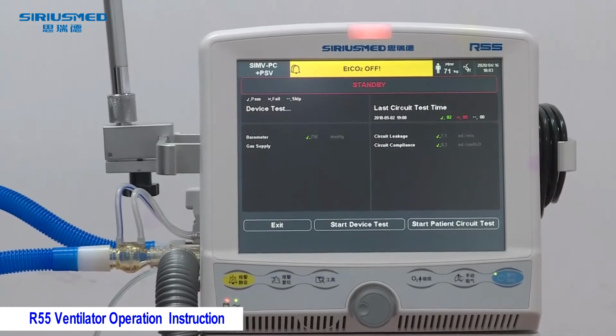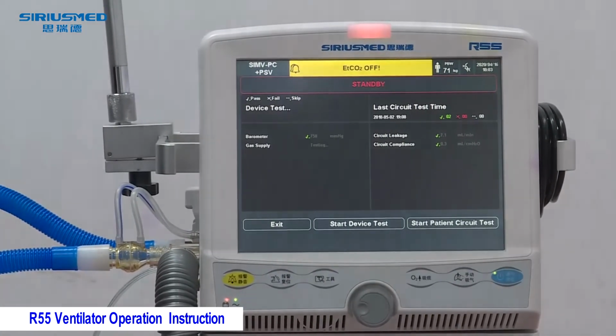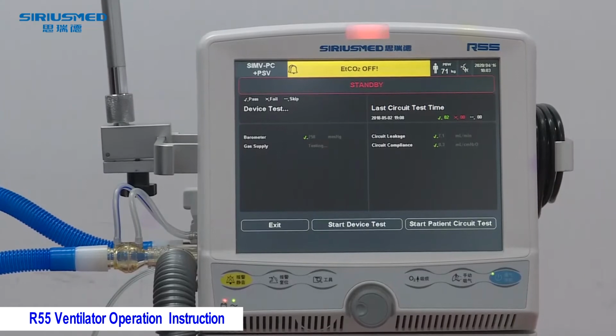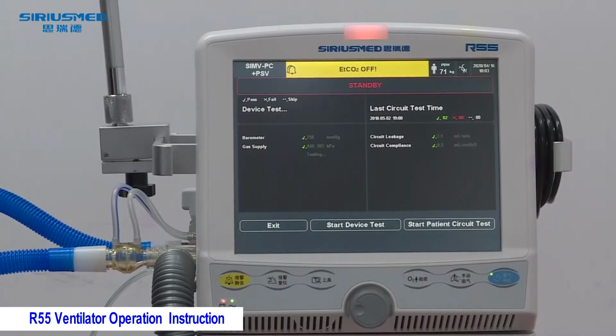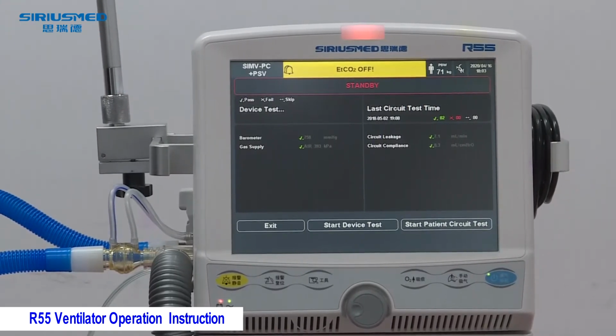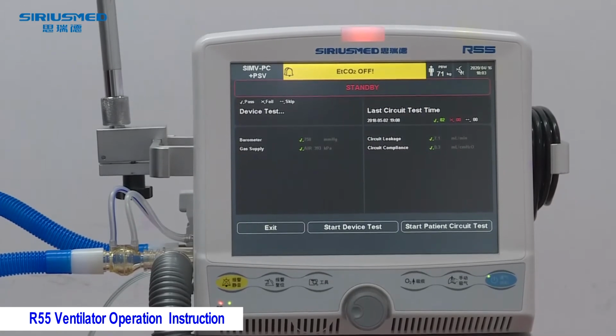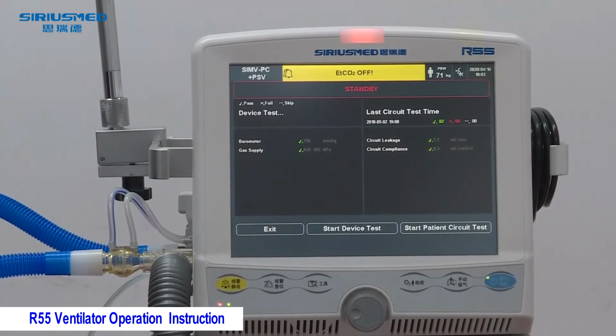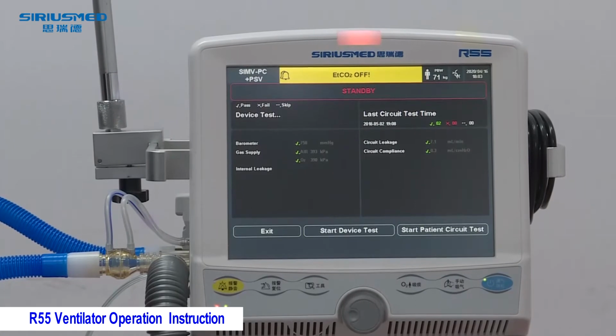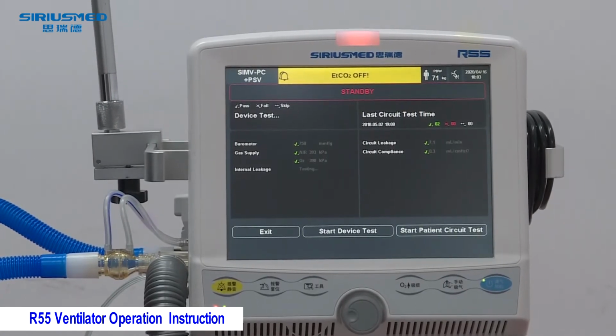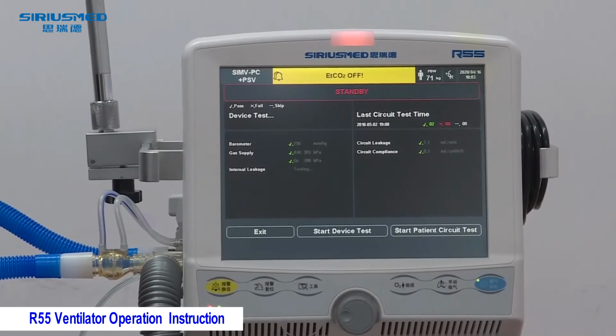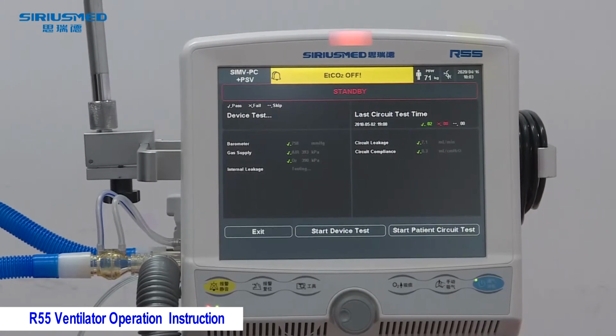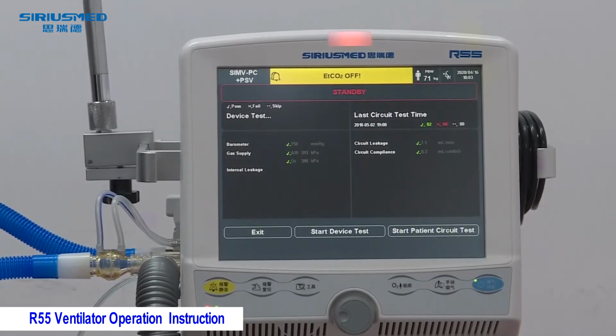And because right now in the office we don't have oxygen, we have skipped the oxygen sensor test. But it's important for the doctor to do the oxygen sensor test. When the hospital connects the oxygen gas supply, the oxygen sensor test will also be done automatically in the device test.